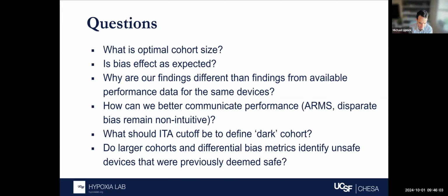I think the concern is if there are a couple of things, and I don't know that I could summarize this in a minute, but we're hearing a lot of calls, for example, that all pulse oximeters should be multi-wavelength. Let's just make them all 8 wavelengths because that seems to be better, and if we do that, then we won't have any problems at all. Or we're hearing from companies who have new technologies that may have solved this problem. Or we're hearing, if regulatory tests have such huge requirements that there's a huge cost change, a study goes from being $50,000 to $2 million per device or probe, that's something we're going to pass on to consumers. Those are three scenarios that we hear.